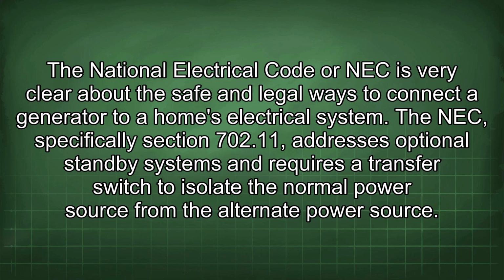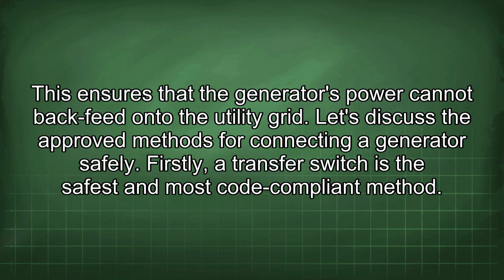The NEC, specifically Section 702.11, addresses optional standby systems and requires a transfer switch to isolate the normal power source from the alternate power source. This ensures that the generator's power cannot backfeed onto the utility grid. Let's discuss the approved methods for connecting a generator safely. Firstly, a transfer switch is the safest and most code-compliant method.